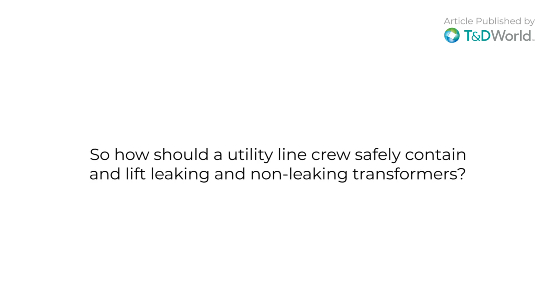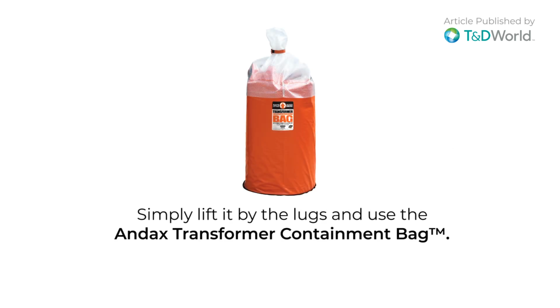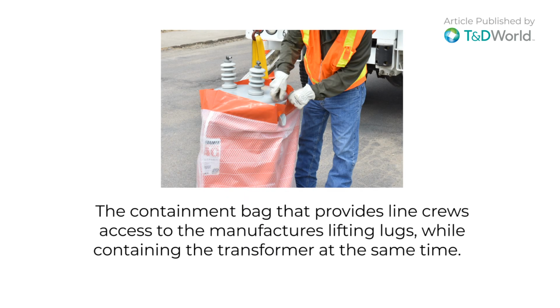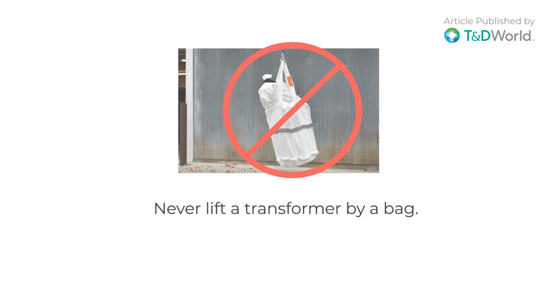So how should a utility line crew safely contain and lift leaking and non-leaking transformers? Simply lift it by the lugs and use the Andax transformer containment bag. The containment bag that provides line crews access to the manufacturer's lifting lugs while containing the transformer at the same time. Never lift a transformer by a bag.